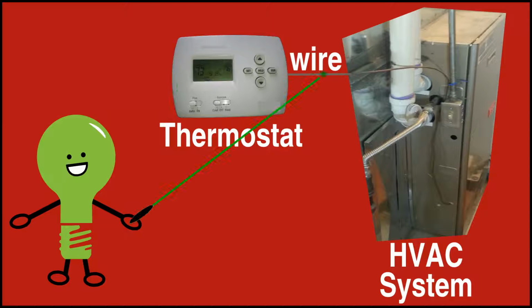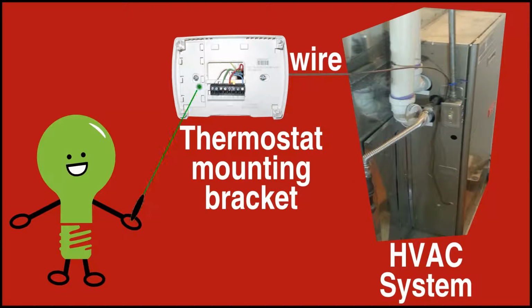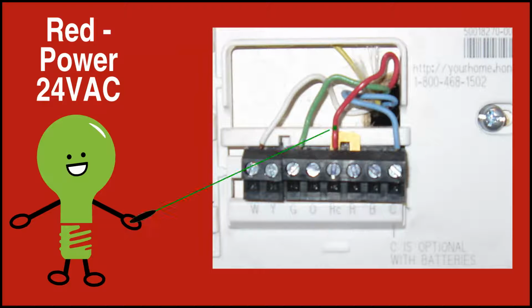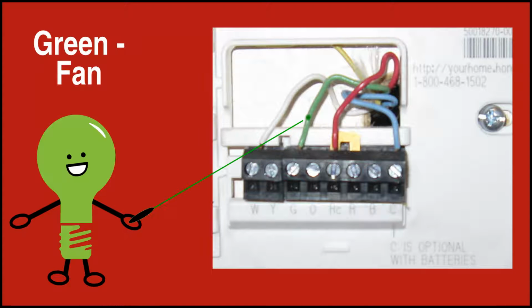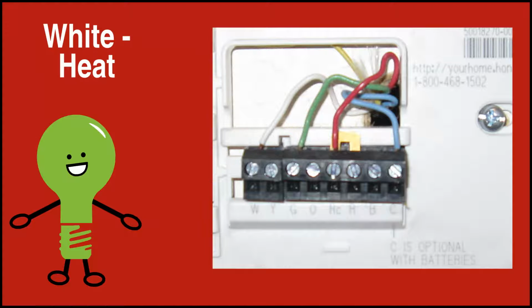The thermostat is connected by a cable to the heating, ventilation, and air conditioning system. If we remove the thermostat from its mounting bracket, we see several wires. The red wire is power. It is a 24-volt AC signal. The green controls the fan. If the red wire power signal is connected to the green wire, the fan will go on. The white wire controls the heating element. If the red wire is connected to the white wire, the heat will come on.